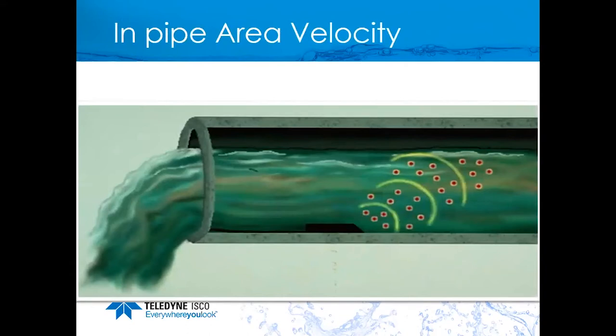An in-pipe area velocity sensor has a pressure transducer to read water depth, giving the wetted cross-sectional area. It transmits a 500 kHz signal into the flow stream and reads the Doppler shift from particles and air bubbles in the water to determine velocity.